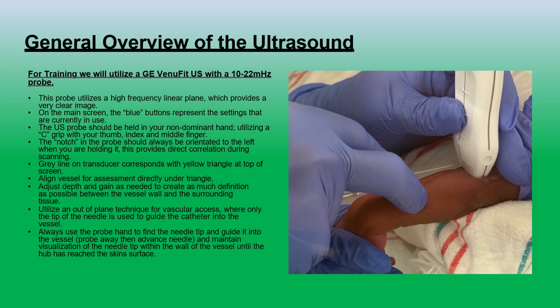You can also see some gray lines on the probe itself. That gray line runs right down where her thumb is, right down the center of the probe. That actually corresponds to a yellow triangle on the ultrasound screen itself. And so it's really important, when we have identified the vessel that we're going to put our catheter into, that we orient ourselves so that the vessel is directly under the gray line, therefore directly lined up in the center of the probe.